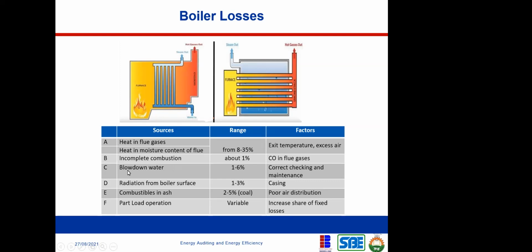Okay. Now, blowdown water, what this simply means is that when you have a boiler, what's happening in your boiler is that you're transforming water into steam, right? Now, sometimes you have scales. Okay, if you have been dealing with water, even in your kettle, depending on the kind of water you have, if you keep boiling water and the water keeps evaporating, turning into steam, sometimes you find out that you have scales, residues, right? Now, sometimes if you don't remove those kind of residues from your boiler, it will cause damage.